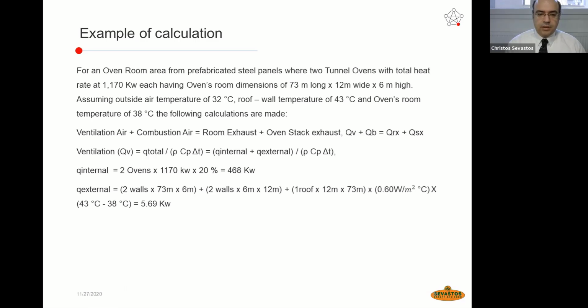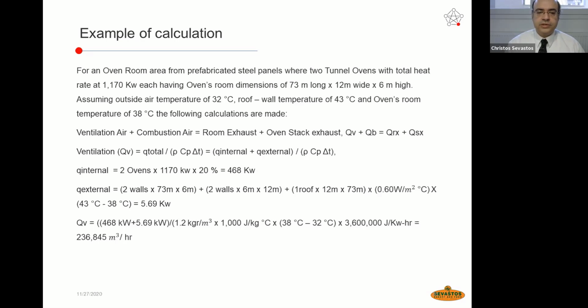Regarding the external heat now, we are going to have 2 walls, 2 different sides for the walls. We're going to have one roof, 73 meters long, 12 meters wide. And this calculation gives us 5.69 kilowatt as external heat, transmitted heat from the walls and from the roof. Just to remind you that we have been assuming roof and wall temperature of 43 degrees.